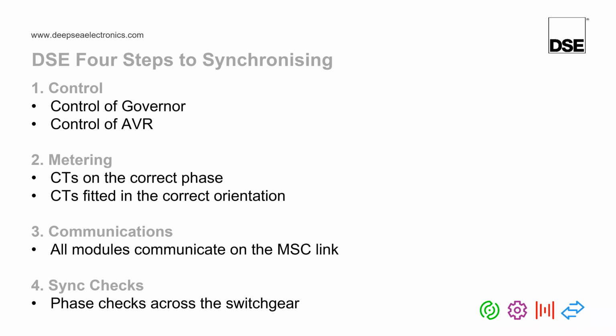So before we go in depth into each of these four steps, I'd just like to pass back to Dave just to see if we've got any questions that have come in. Yes, we've had one gentleman ask, what allowable AVR analog percentage when the generator is running? We're effectively aiming for 75 to 85% when setting up switch 2, but Ash will be covering this shortly. Another gentleman's asked, does the percentage of kVAR have to be equal? When synchronizing, yes, the percentage of kVAR is shared equally across the sets, assuming they're the same size, but it's the percentage that is equal.